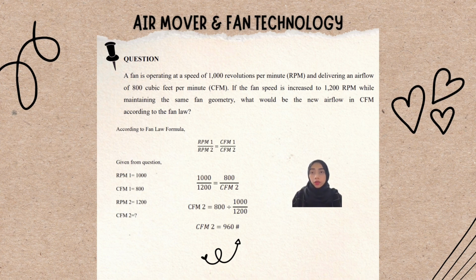For this presentation, I will explain the questions for air mover and fan technology. The question is given as: a fan is operating at a speed of 1000 revolutions per minute and delivering an airflow of 800 cubic feet per minute. If the fan speed is increased to 1200 RPM while maintaining the same fan geometry, what would be the new airflow in CFM according to the fan law?